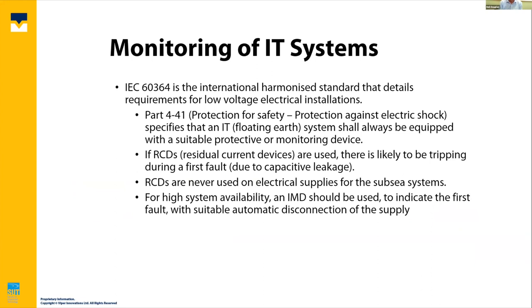And I am building a story here. This looks a pretty boring slide quoting IEC numbers and different parts. But fundamentally, if you have an IT system, you absolutely have to have a suitable protection or monitoring device installed. So if your offshore system complies with international standards, you have to have a protective device.